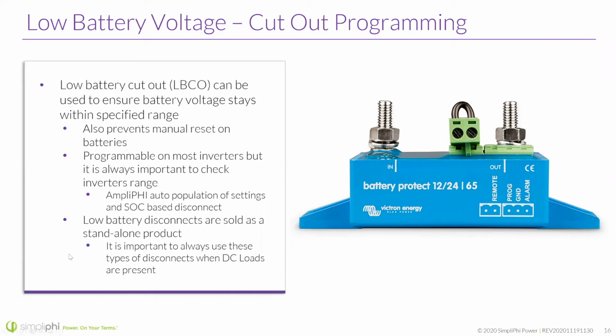DC loads are kind of interesting in a way. Let's say you have an inverter that you're using AC loads with, and you have DC loads on a system. The inverter might go into low battery protection mode when the voltage hits, let's say, 48 volts. And that'll stop the AC loads from pulling from the battery until the battery's at a better state of charge. But the DC loads are not going through that inverter, and they will continue to pull, typically, if left unmitigated, and pull the battery down below that. So I can't tell you how many times I've seen that too.